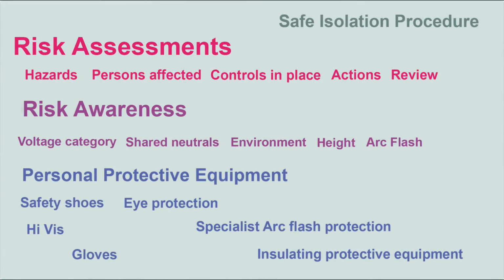So the safe isolation isn't just a test procedure, it's everything that goes with it as well. You have your risk assessments where you work out the hazards and who's affected, controls that are needed, any actions and how you're going to review it. And you need good risk awareness, you need to know what voltage category you're working at. It's good to have a knowledge of shared neutrals, where a circuit you think is isolated is not. It's energized by the neutral from another circuit. I've got a video on that. Got to consider your environment, height, arc flash. You have to be aware of what the potential risks are. And if you need any personal protective equipment, your basics, your Hi-Vis, your safety shoes, eye protection, gloves, up to specialist arc flash protection and insulating protective equipment.